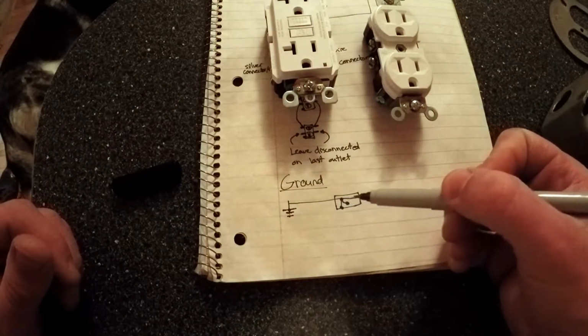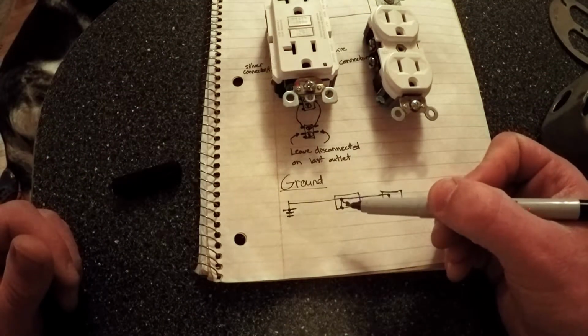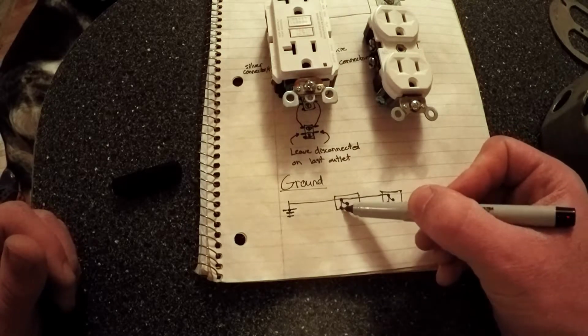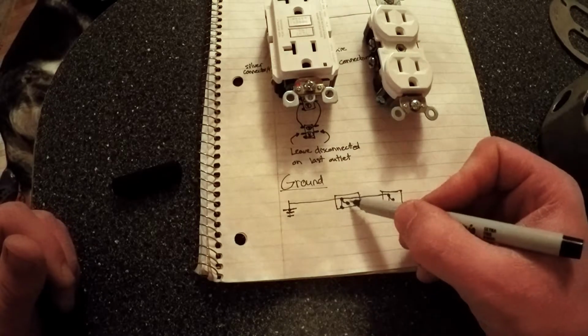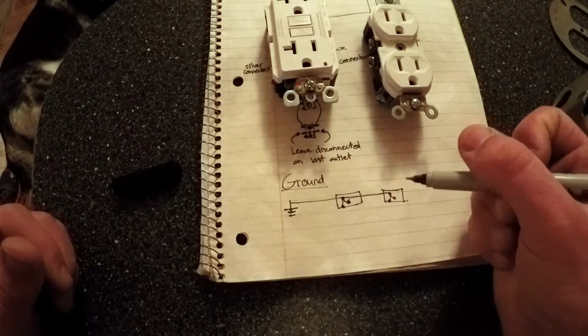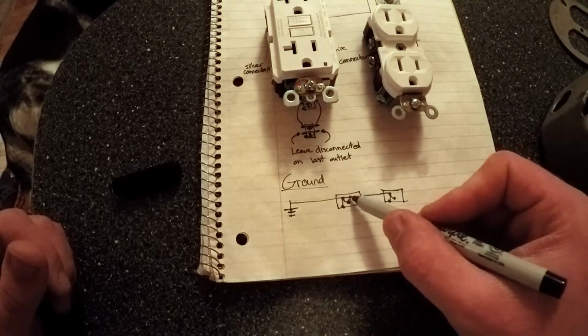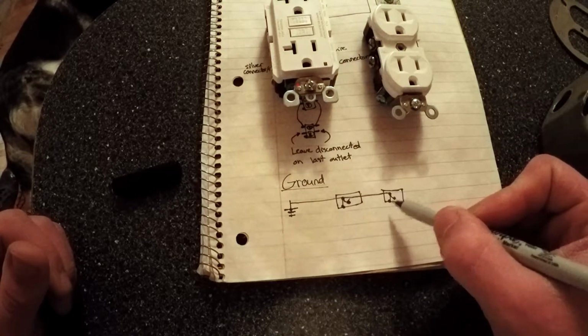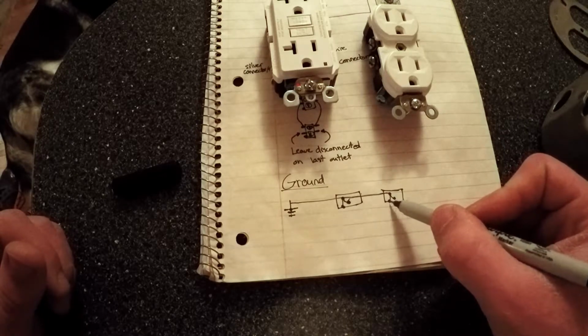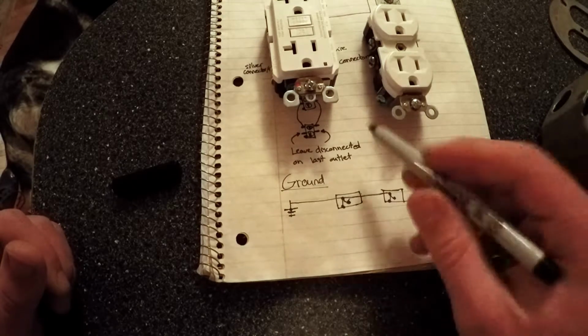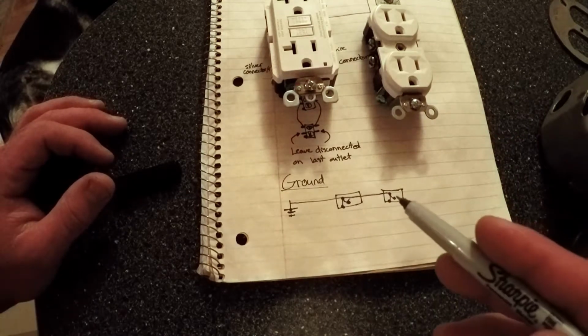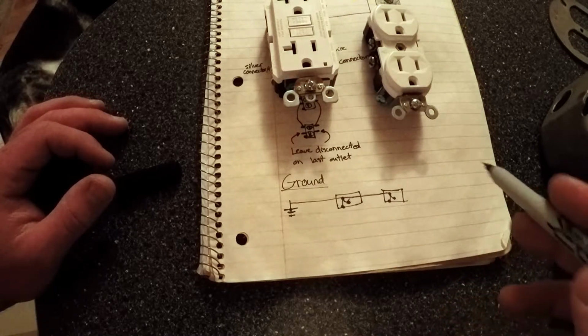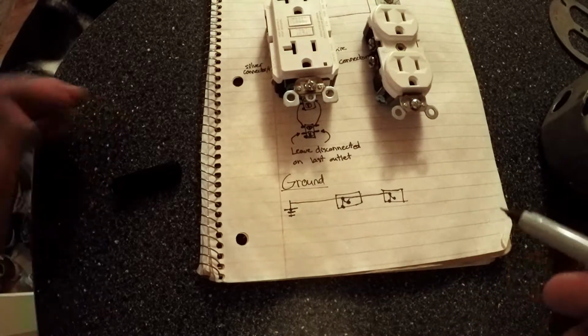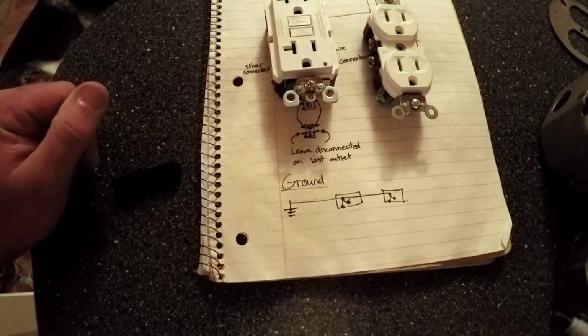So once you're in the junction box, you're going to tee off. One is going to connect here to the junction box itself, and the other one's going to connect to that green prong on your outlet. After the first outlet, it just continues to go, and then you do the same thing on the second outlet. Tee off, you grab the second junction box, and you grab the second outlet. Every outlet after that's going to be pretty much the same thing—it just keeps going, and you tee off to the outlet in the junction box, all the way until the end of your series.